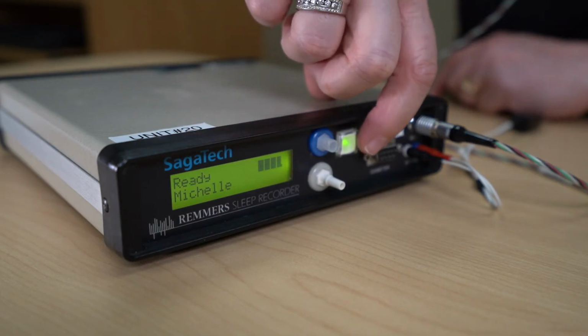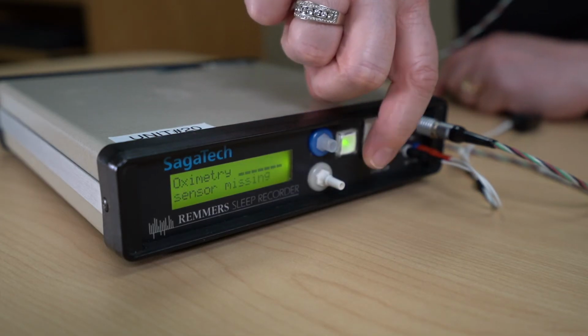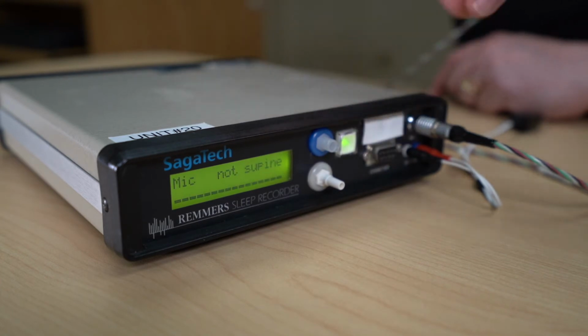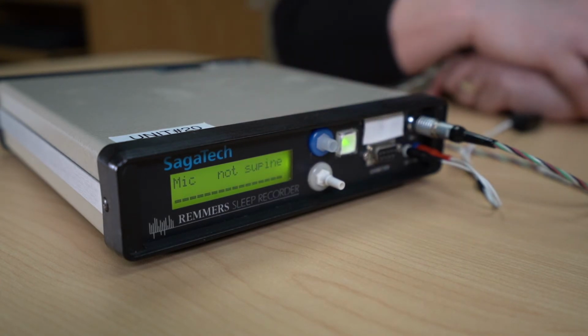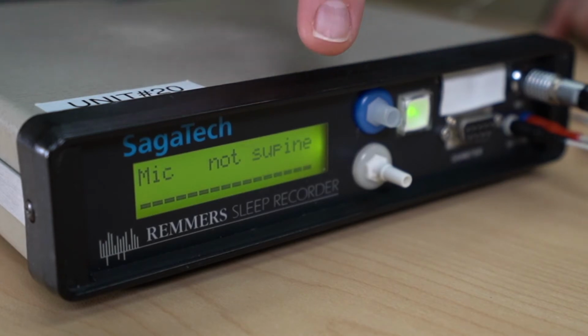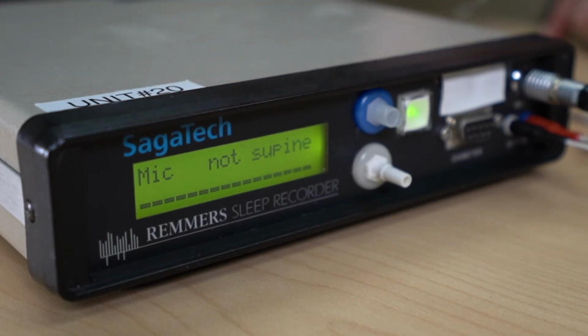Press and tap the green lit button on the recorder to scroll through the menu until you see mic appear in the screen. Say hello. Hello. You should see the bar indicators appear in the screen. If you do not see strong movement on the bar indicators, you may need to reposition the sensor up or down to achieve a good signal. You will also see the word not supine. The Snore Sensor senses your sleeping position. Not supine means you are not on your back.